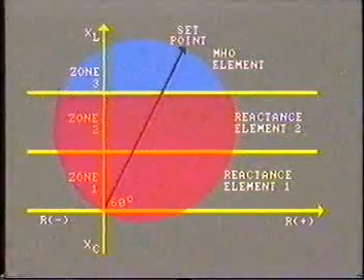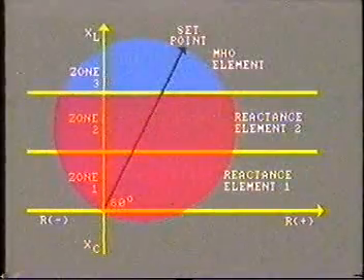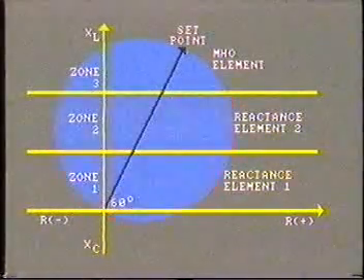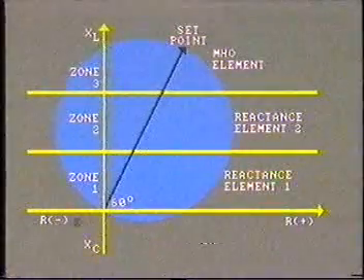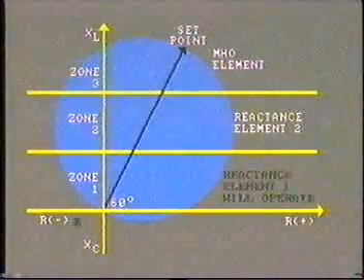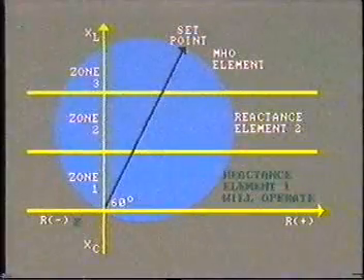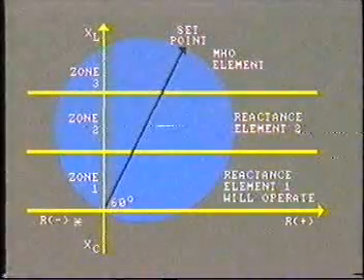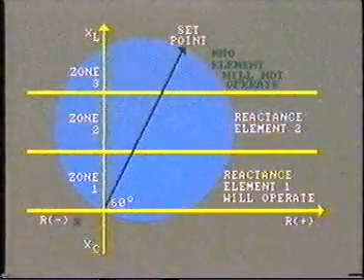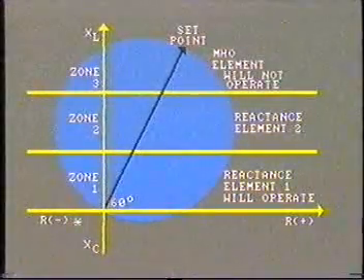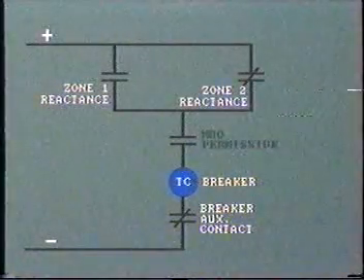The permissive contact will only close when the impedance falls within the circle. If the fault is upstream, the reactance relay will operate. But its tripping circuit will be incomplete, because the Mho relay will not have operated, and the permissive contacts remain open.